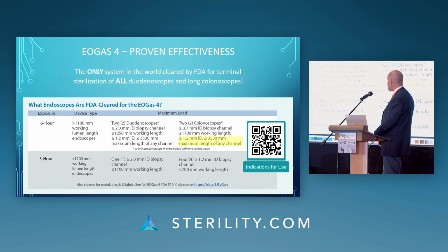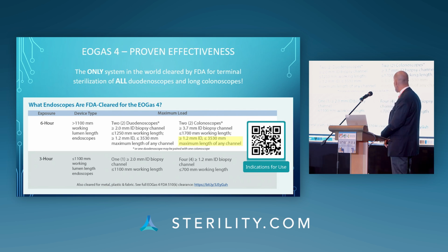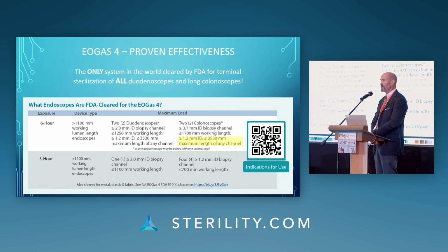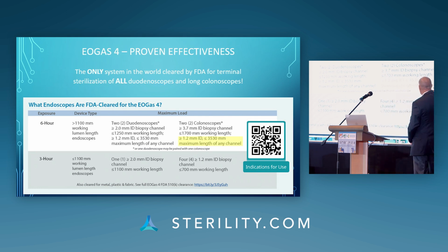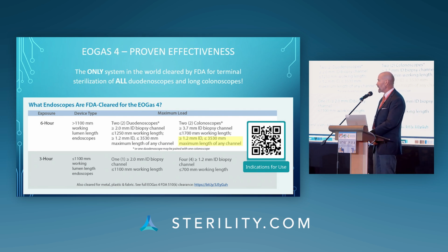This is a summary from our FDA 510(k). I will draw your attention to specifically the length and diameter of endoscope lumens that we are able to sterilize. That is this right up here. We have been cleared to sterilize lumens that are over 3,500 millimeters in length and equal to or greater than 1.2 millimeters in diameter. This is about an 11-foot scope, almost 4 meters.